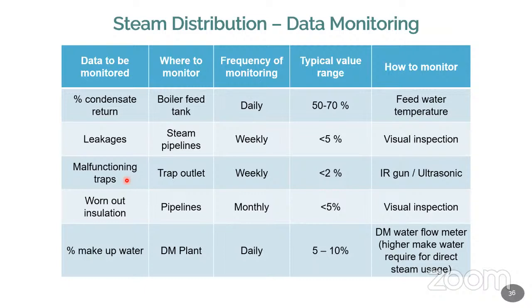Probably weekly you have to check the trap with the help of a thermography gun, or sometimes a screwdriver can be used to check whether there is any hammering effect. Then worn out insulation. This is again visual inspection. When the insulation fails in the boiler system or steam pipeline or wherever, it should be properly inspected and rectified. Then the percentage of makeup water should be monitored and measured daily.